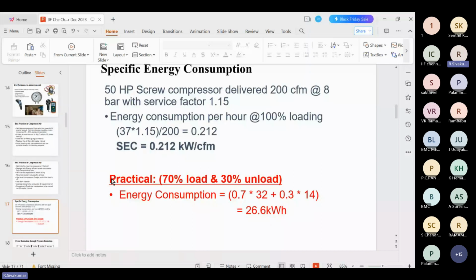Then, how to arrive at the specific energy consumption. Take a 50 HP screw compressor delivering 200 CFM at 8 bar with a service factor of 1.15. Service factor means the OEM designed the compressor motor to take another 10 to 15% extra power to withstand that much pressure. Every manufacturer gives it, and it is mentioned on the nameplate of the motor itself. Few manufacturers give 1.2, some give 1.1 to 1.15.